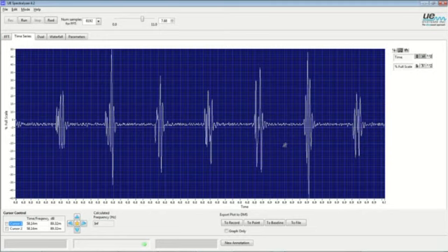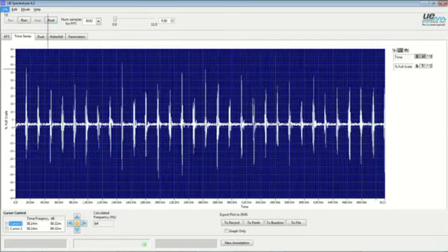So this was very early stages, and this ringing as the discharges occur takes place for longer and shorter periods. The easy fix to this particular insulator was simply to clean it up, and this all went away.